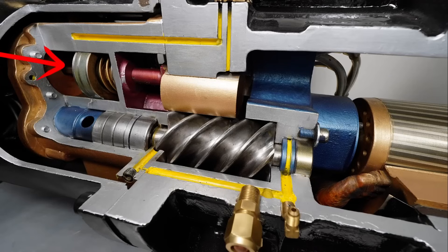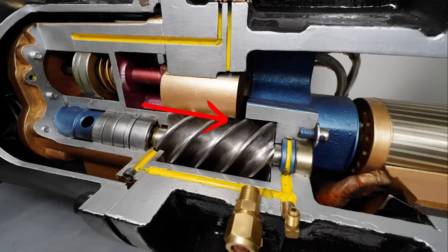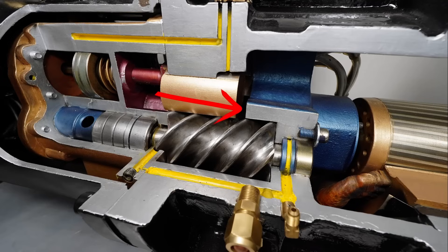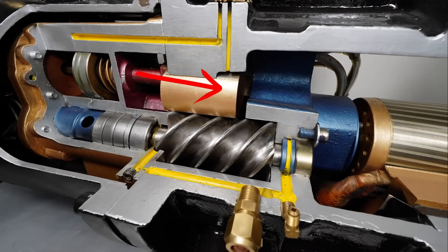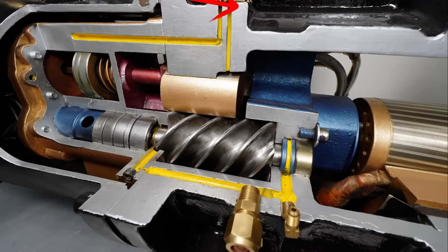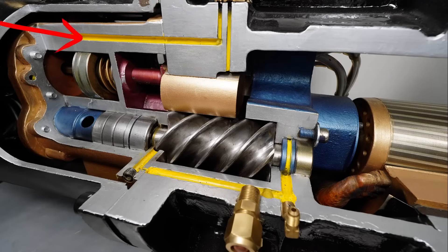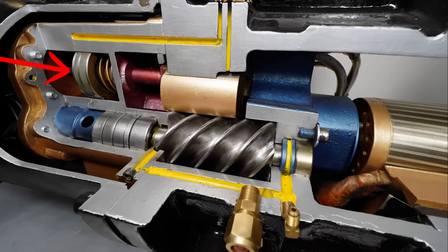And that allows our compressor to run at a fully unloaded state. Now, this is not the Trane compressors that we're discussing here. This is a Hanbell. It's a different style, but we have a very similar slide mechanism. So you can still kind of see the visual and how we have internal oil ports that tie into some solenoids that we can then route and get the oil, use the high pressure oil to actuate this piston.